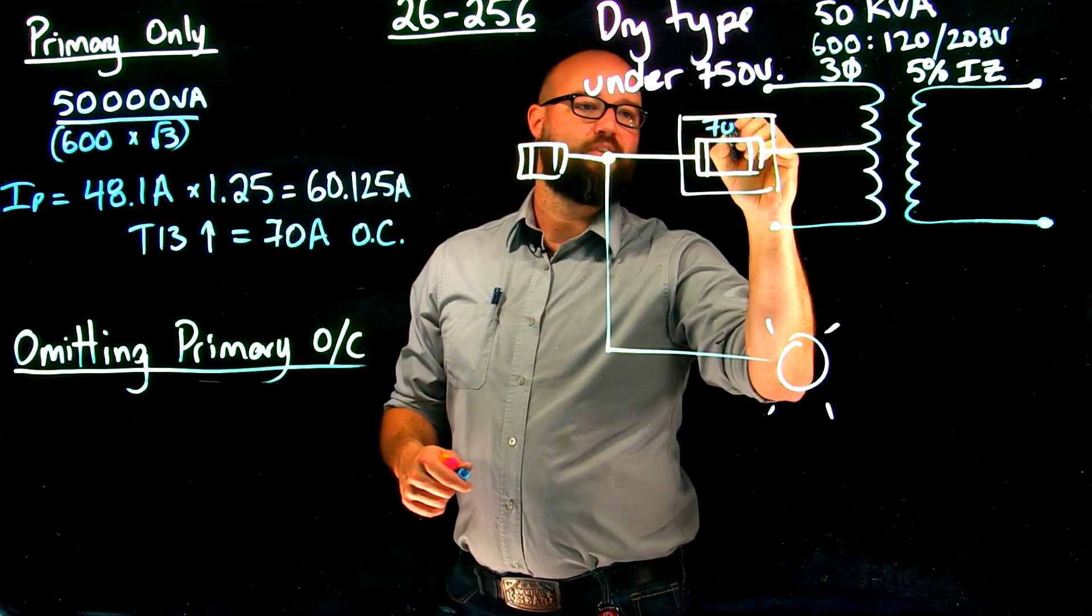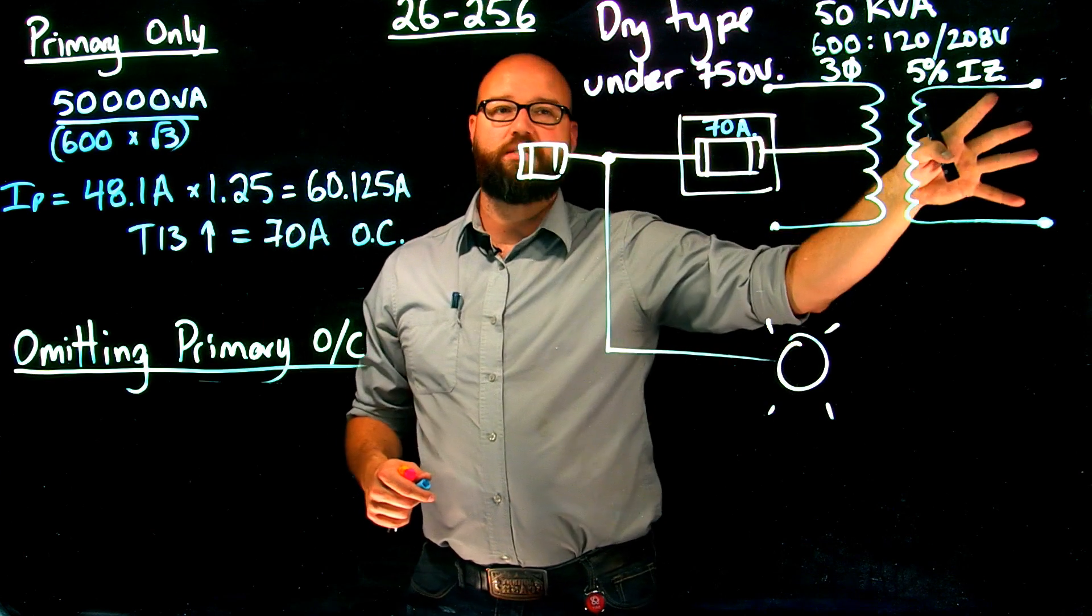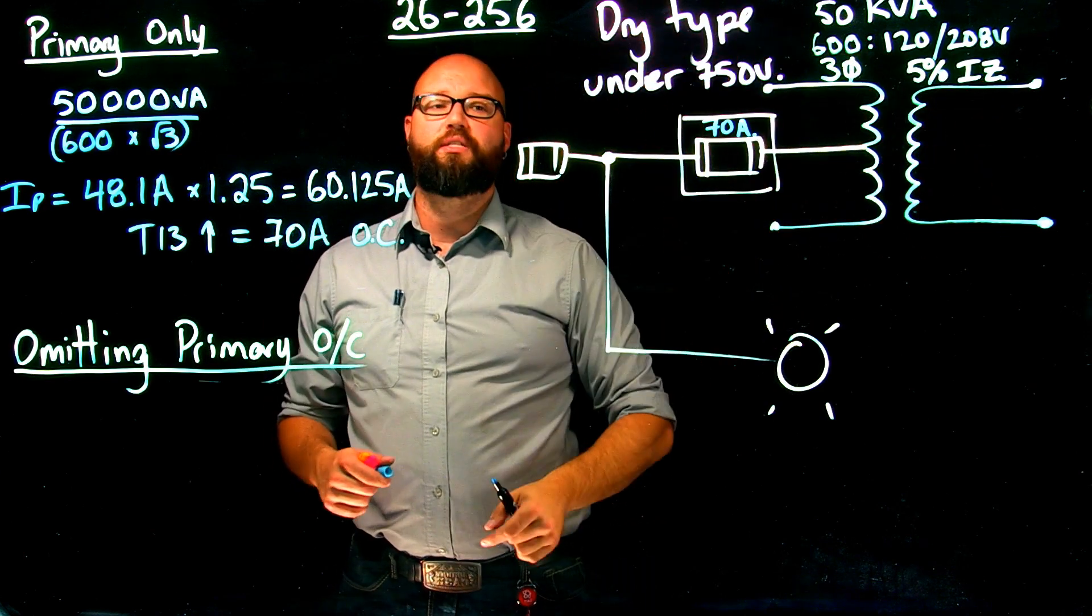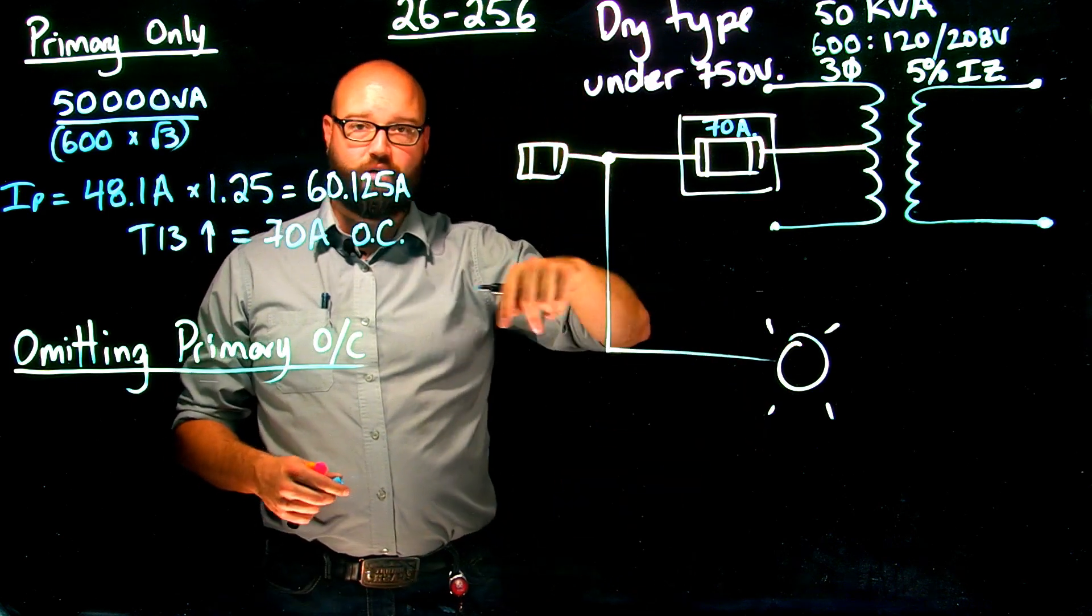and we are going to choose a 70 amp overcurrent. So this would become a 70 amp overcurrent. That would adequately protect our secondary side, it would adequately protect our primary side. Again, primary feeder, we're not going to worry about right now. That's the next thing we're going to do.